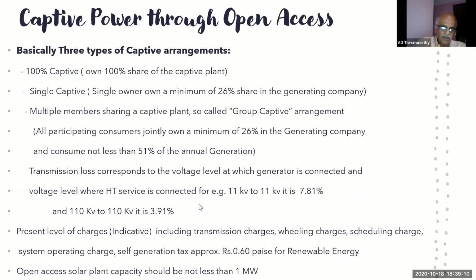Any renewable power, especially an open access solar plant - if you are putting the solar plant anywhere - it should have a minimum capacity of 1 megawatt. This is not applicable to wind, only to solar plants. A minimum of 1 megawatt solar plant has to be provided to get connected to the grid. This is basically about the captive arrangements in open access.